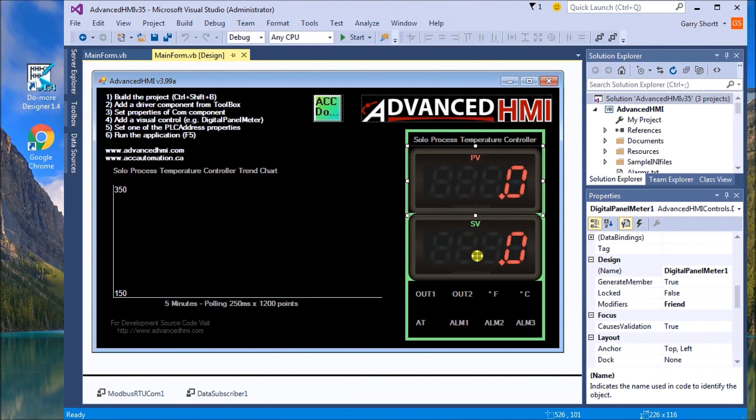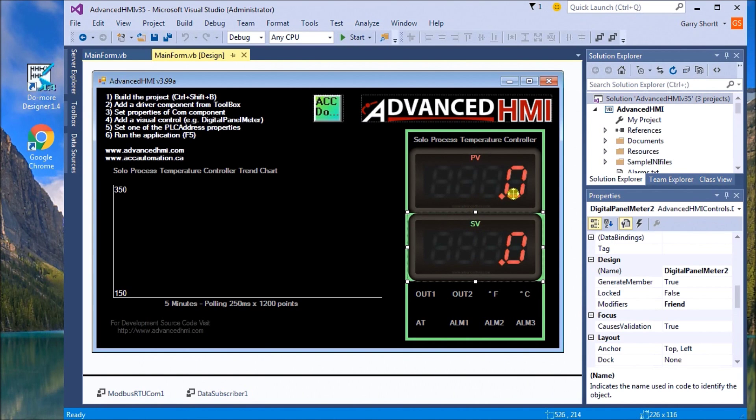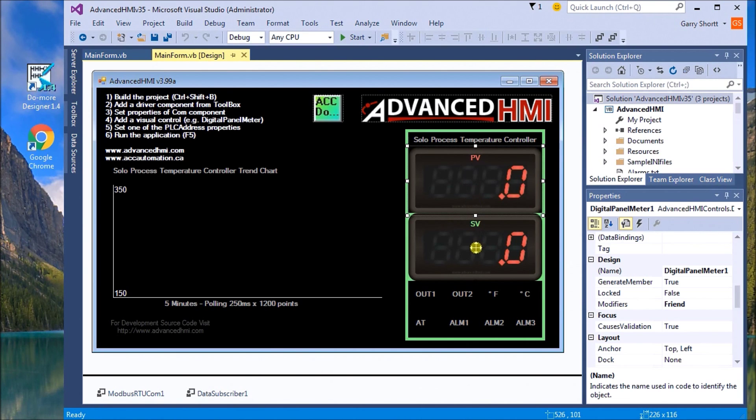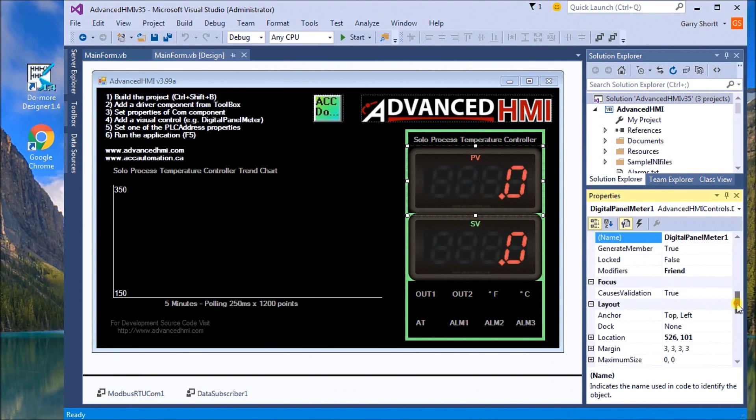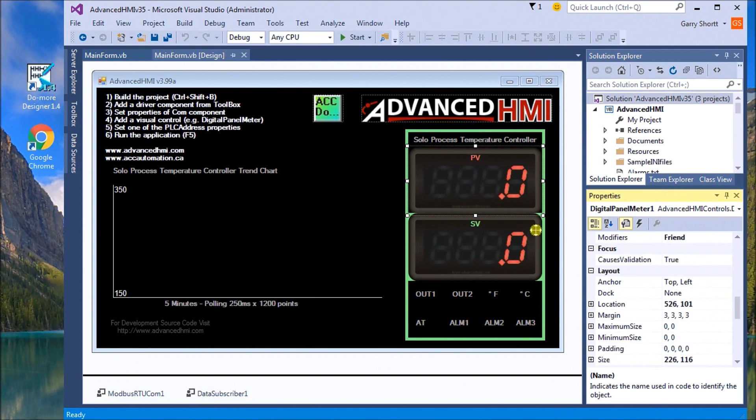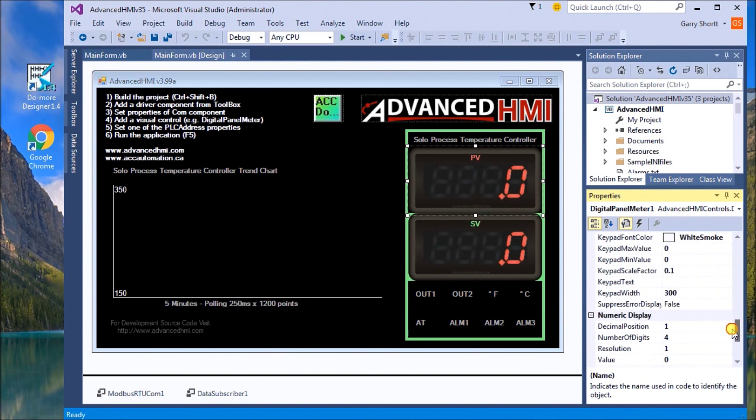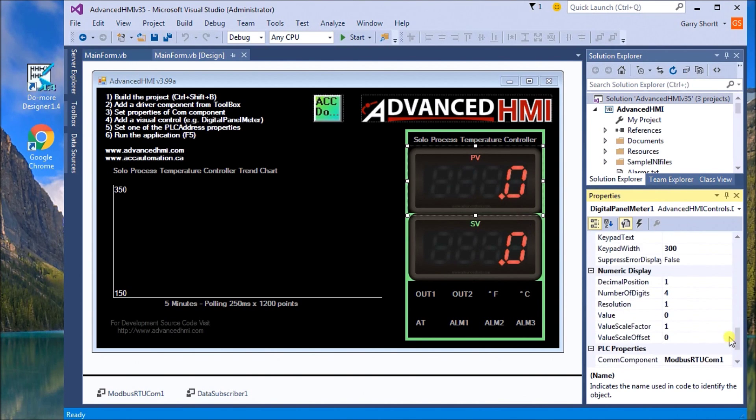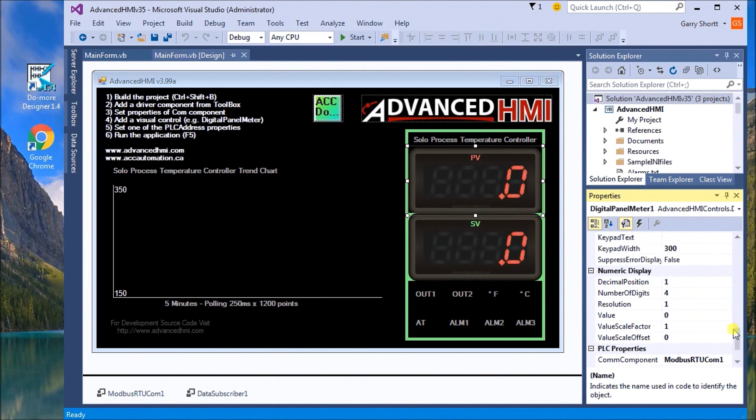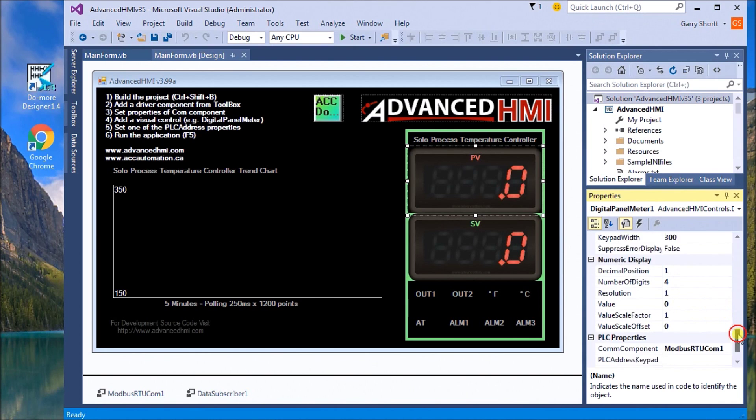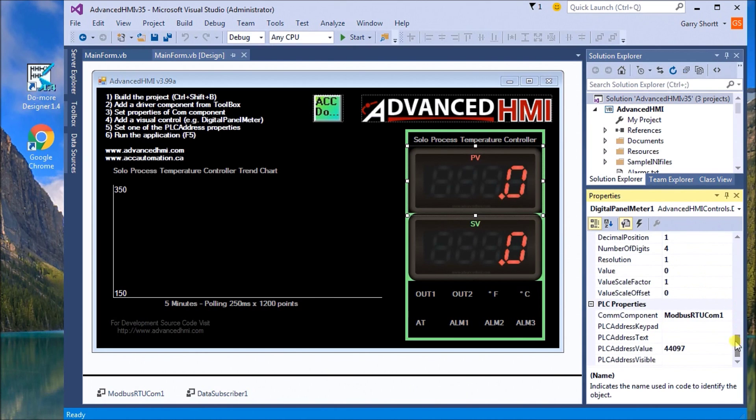One for the PV value (present value) and one for the set value SV. You'll notice that on my present value and set value I have a decimal point. I have one decimal place, four digits, resolution of one, and on my Modbus we're going to be talking Modbus RTU comm number one.